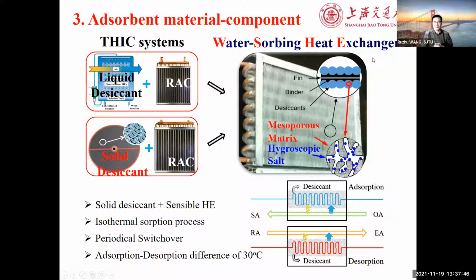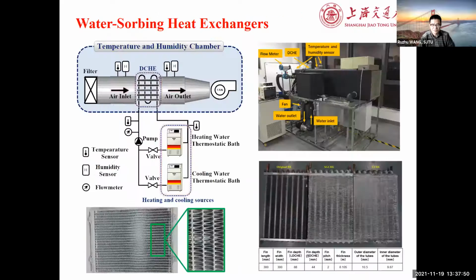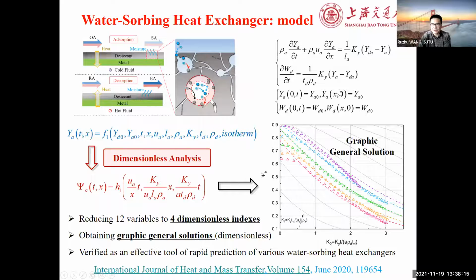This was developed first by Shanghai Jiaotong, and then we did some research. This just shows a desiccant heat exchanger in the air duct. So we have heating and cooling, and normally about a 30 degrees temperature difference, so cooling could be about 15 degrees and heating about 45 degrees. This shows the original heat exchangers, and then we coat them with desiccant and do the test. This also shows the measured data. We had to do a dimensionless analysis because there is too much specific data, but in the end we treated only 4 integrated parameters. So we use 4 dimensionless indexes and obtain a graphic general solution.